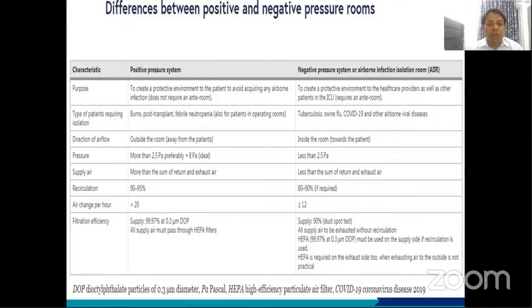Pressure: more than 2.5 Pa, preferably +8 Pa, whereas it is less than 2.5 pascals in negative rooms. Supply air is more than the sum of the return and exhaust air, versus less than the sum of return and exhaust air. Recirculation is 90 to 95% in positive pressure systems, whereas 80 to 90% if required in negative pressure rooms. Air exchanges per hour: more than 20 in a positive room, more than or equal to 12 in a negative room.